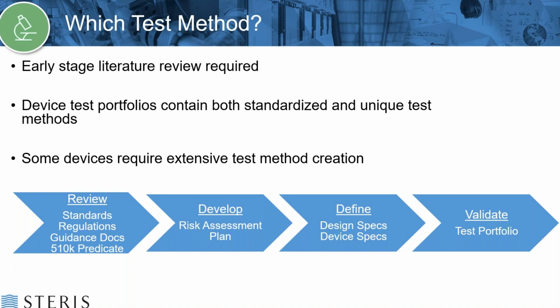So you're going to review standards and regulations, and you're going to develop a plan. So all of this testing is based on your risk assessment. The higher the risk, the more testing typically you need to do. You're going to define all that testing within your device and design specifications. And then you're going to go through your validation phase, and you're going to test your product and its packaging to ensure that all of the requirements that you have are met.